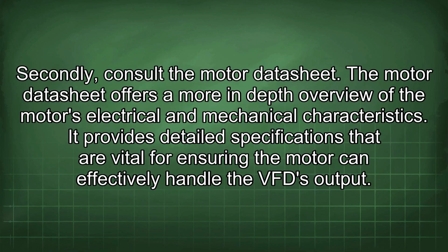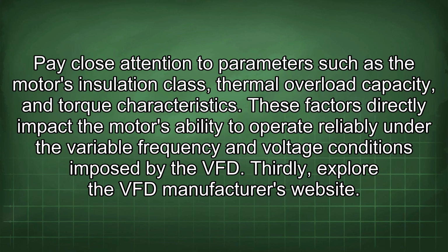Secondly, consult the motor datasheet. The motor datasheet offers a more in-depth overview of the motor's electrical and mechanical characteristics. It provides detailed specifications that are vital for ensuring the motor can effectively handle the VFD output. Pay close attention to parameters such as the motor's insulation class, thermal overload capacity, and torque characteristics. These factors directly impact the motor's ability to operate reliably under the variable frequency and voltage conditions imposed by the VFD.